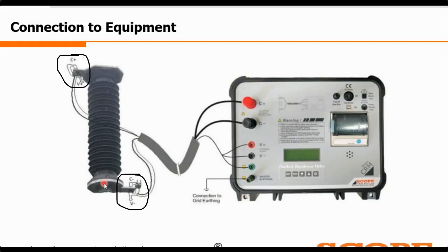So at the two ends of the two flanges, you will be keeping the C plus and C minus terminal, and you are through. With that, you can get the total breaker, both the contacts put together, you will be getting the series resistance. But if you are interested in per interrupter resistance, then it will be just like that.